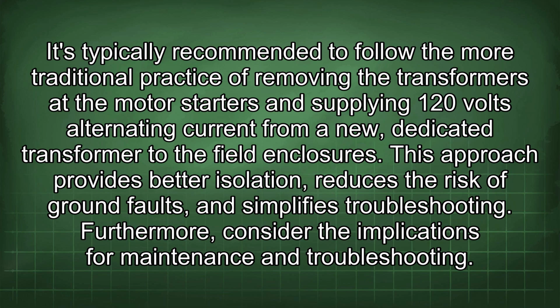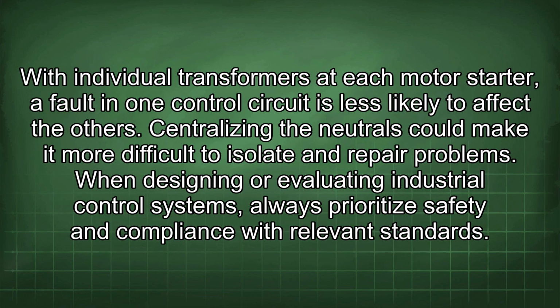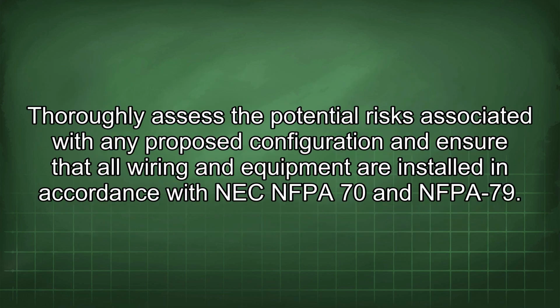Furthermore, consider the implications for maintenance and troubleshooting. With individual transformers at each motor starter, a fault in one control circuit is less likely to affect the others. Centralizing the neutrals could make it more difficult to isolate and repair problems. When designing or evaluating industrial control systems, always prioritize safety and compliance with relevant standards. Thoroughly assess the potential risks associated with any proposed configuration and ensure that all wiring and equipment are installed in accordance with NEC NFPA 70 and NFPA 79.